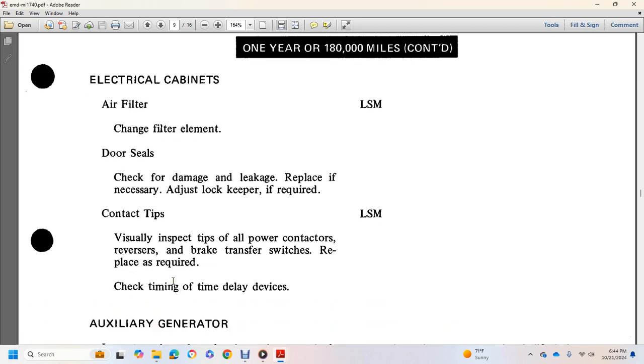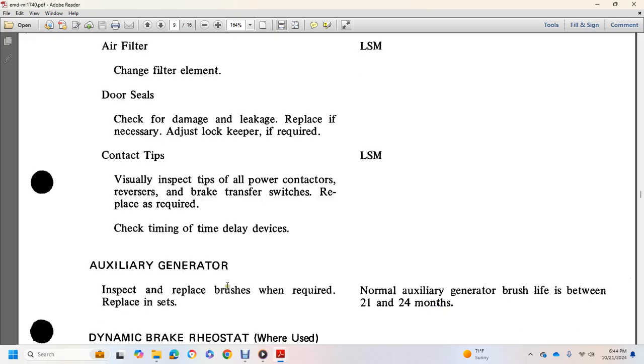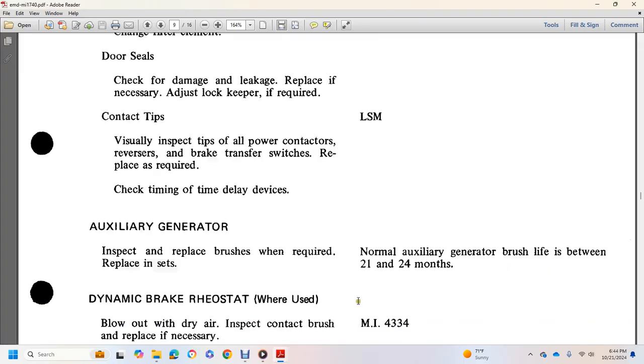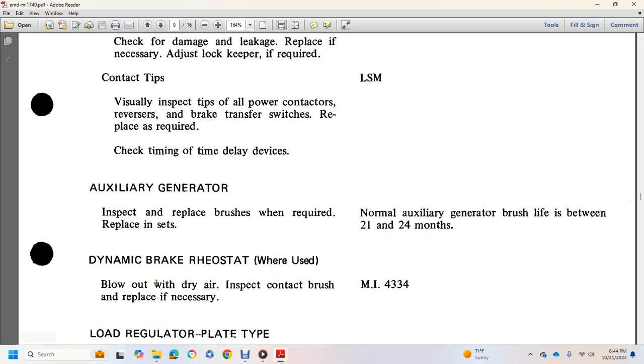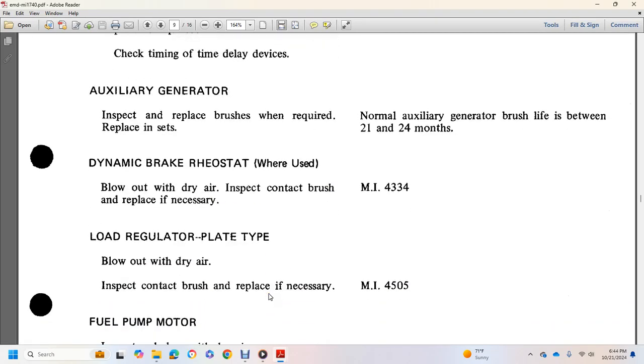Visually inspect tips of all the power contactors, reversers, and brake transfer switches; replace as required. Check the time of the timing delay device. Auxiliary generator: inspect, and replace brushes when required, replace in sets. Normally, auxiliary generator brush life is between 21 and 24 months. Dynamic brake rheostat where used: blow out with dry air, inspect with the contact brush, replace if necessary, maintenance instruction 4334.